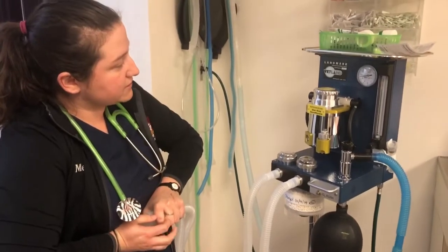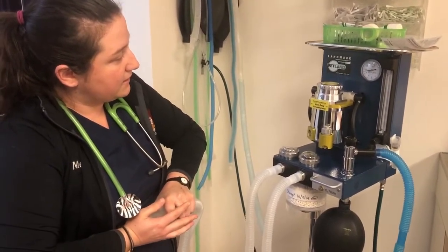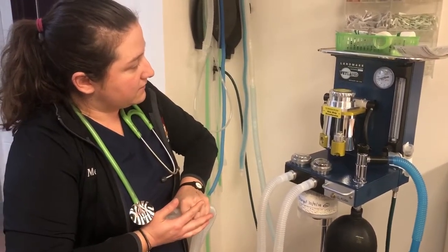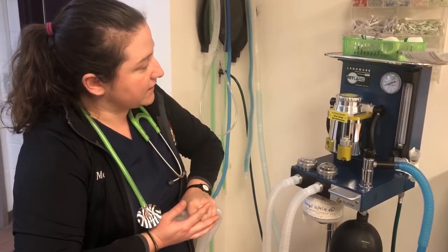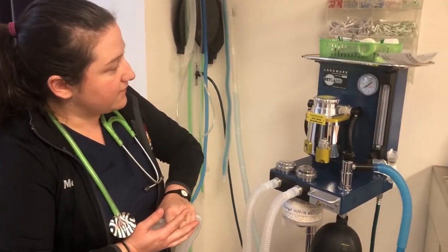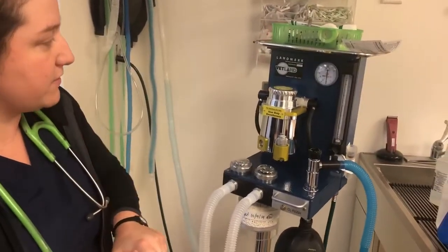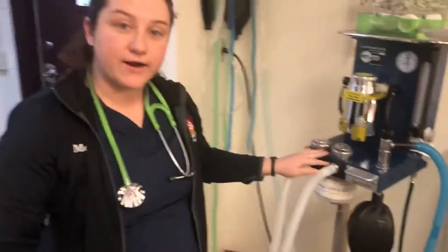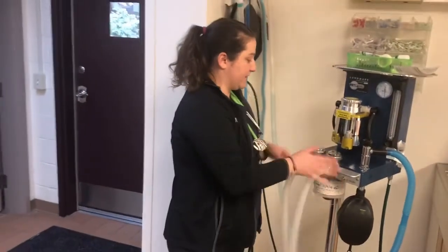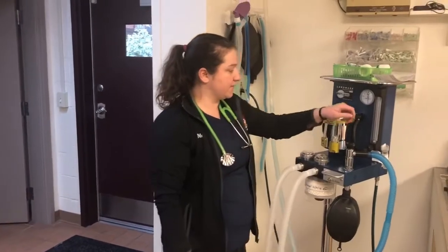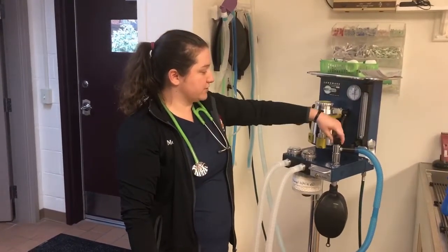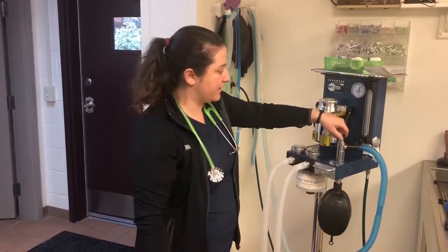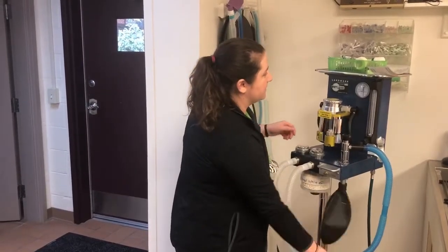and so that means that nothing's leaking. If the pressure were to slowly drop like that, that would indicate that there was a small leak somewhere, so that I would want to check all my tubes and my reservoir bag, make sure there's no holes or cracks in anything, make sure that everything is tight. And then you always want to make sure you reopen the pop-off valve so that it's ready for the next patient.